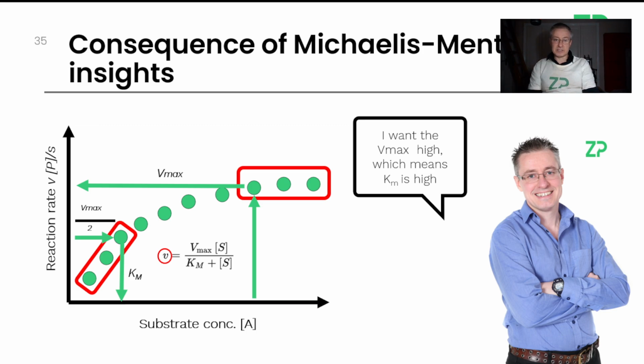In life it's always a bit of a balance. But in general, as a rule of thumb, high Vmax is good because it gives us a lot of signal. But understand there are exceptions: you can end up trying to drive too much reaction, get too much signal, and end up consuming the analyte of interest, and then it will start giving you weird results where you find it hard to get a signal that is linear to the substrate concentration because you're consuming the substrate so quickly.